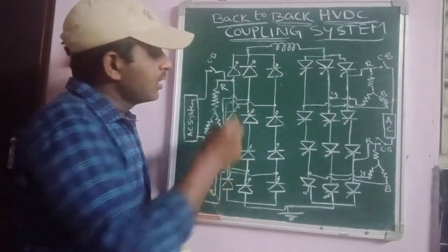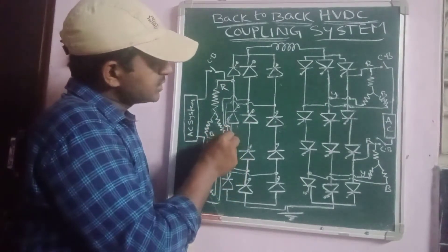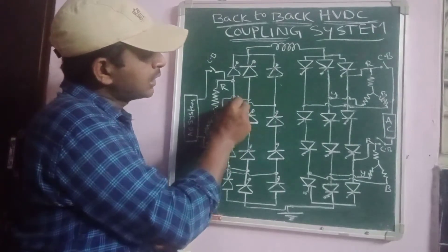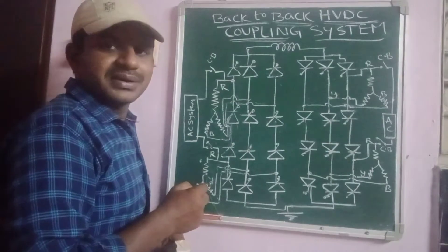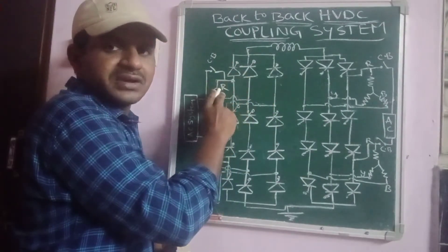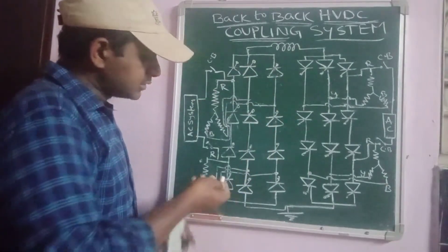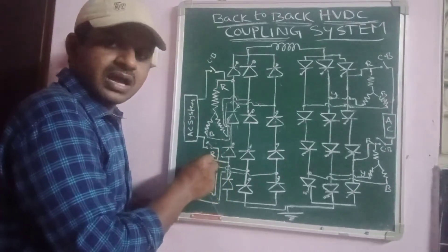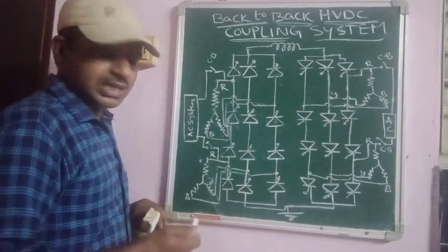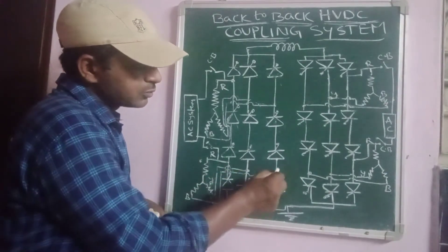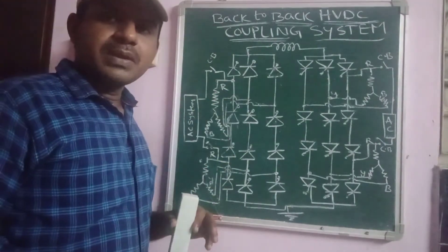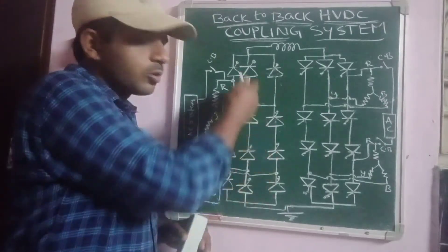The R phase of the transformer is connected to the R phase of the converter station, the Y phase of the transformer is connected to the Y phase of the converter station, and the B phase of the transformer is connected to the B phase of the converter station. Similarly, for the second transformer, R to R, Y to Y, and B to B connections are made. According to this connection, this is called a 12-pulse converter unit.